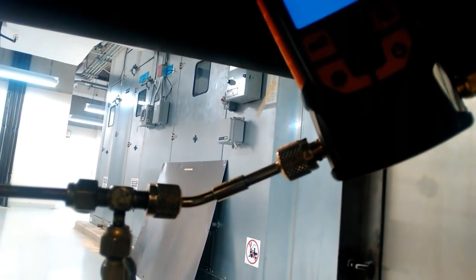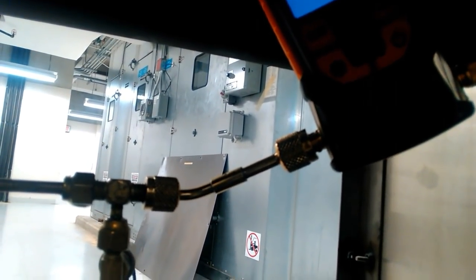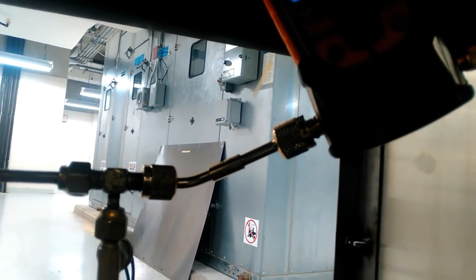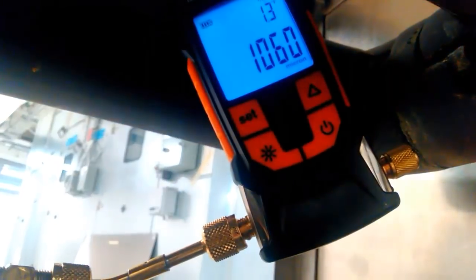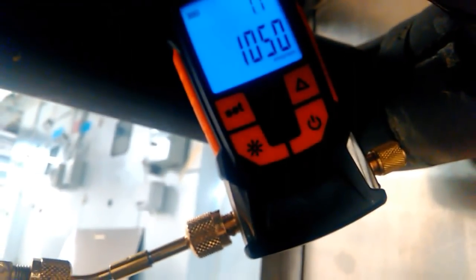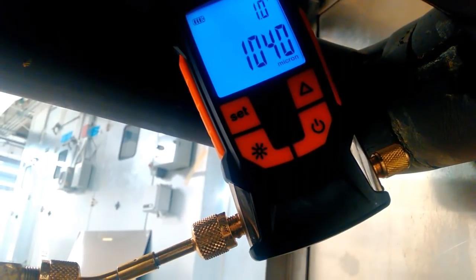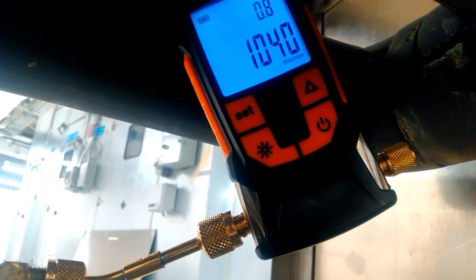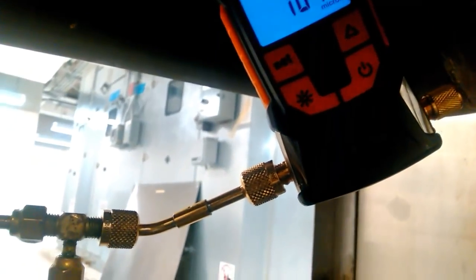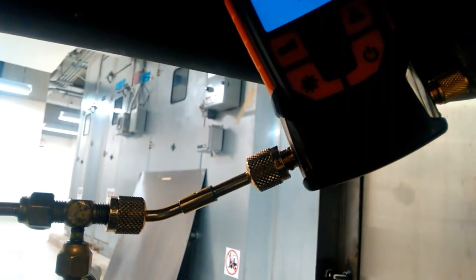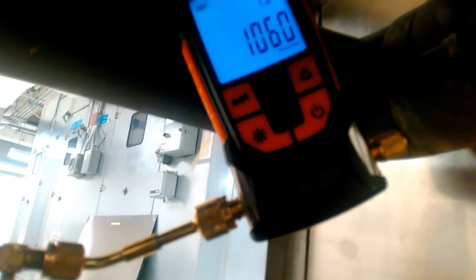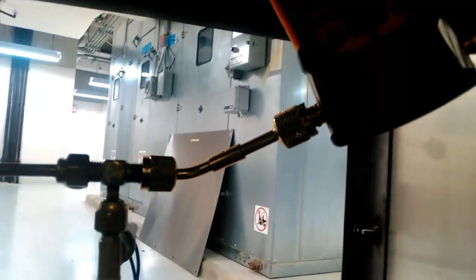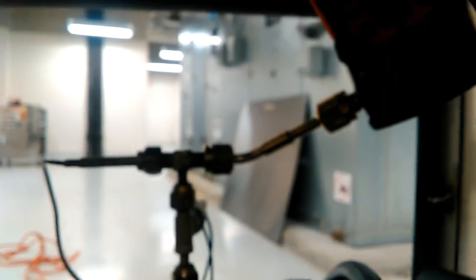Something important to bring up here. Did you notice the coupler I'm using? How it's on a 45? Well, it keeps that micron gauge above the connection point. The reason for that is we don't want system oil getting into our micron gauge, because that could cause problems with the gauge itself. When it's upright like that, oil doesn't have a chance to flow upward towards the gauge. That's a good way to protect your gauge.